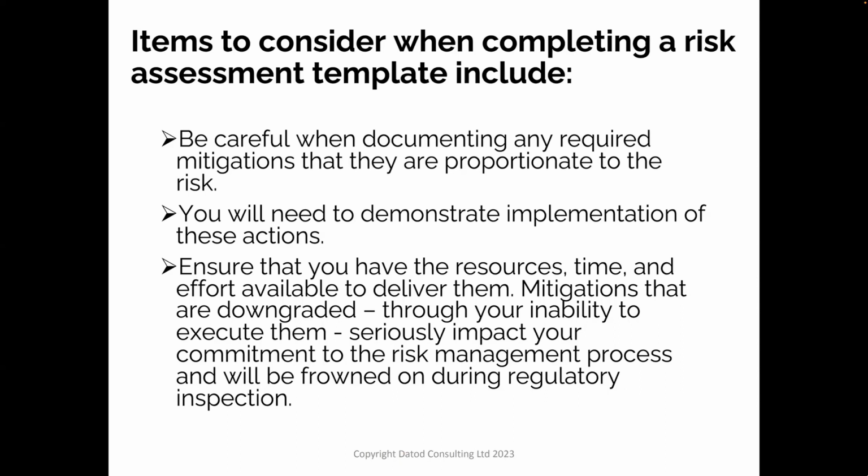Very often you can downgrade mitigations, but it undermines your commitment to the risk management process if they see that you've set these high expectations and then revised the document to bring it down because you decided either you haven't got the resources to do that, or those resources are now competing with something else. So be very careful what you promise within the risk assessment tool, because those are commitments to reducing the risk, and you need to be aware that these documents are quality records that will be scrutinized by regulators, not just the end product, but how they were derived over time during the development of the product.